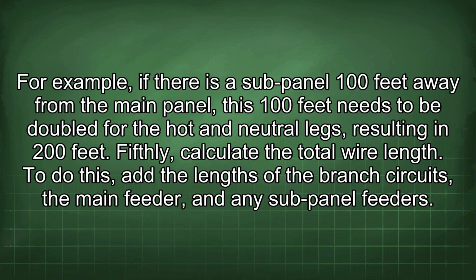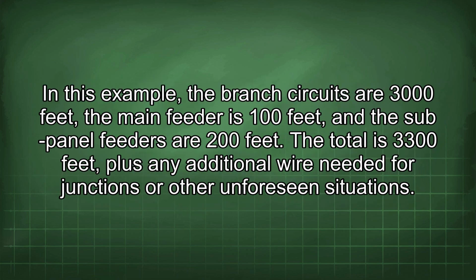Fifthly, calculate the total wire length. To do this, add the lengths of the branch circuits, the main feeder, and any sub-panel feeders. In this example, the branch circuits are 3,000 feet, the main feeder is 100 feet, and the sub-panel feeders are 200 feet. The total is 3,300 feet, plus any additional wire needed for junctions or other unforeseen situations.